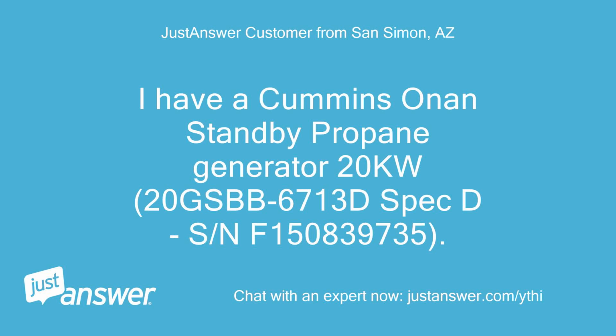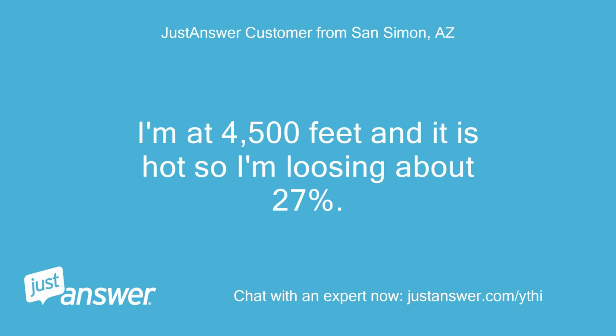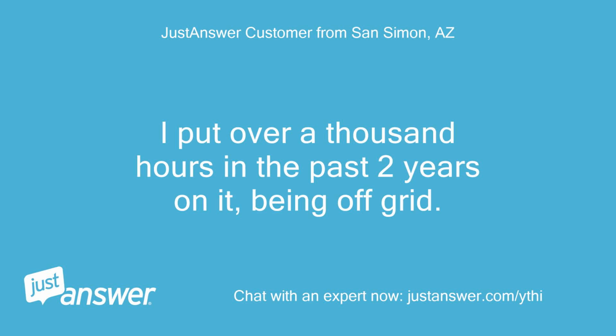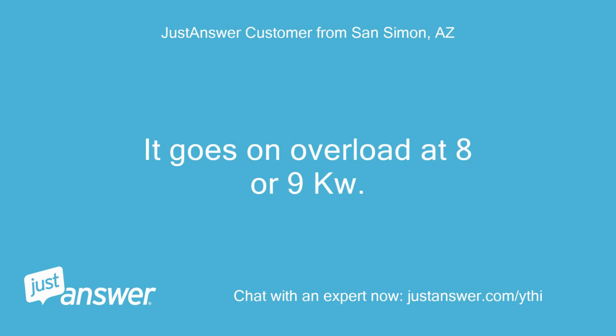I have a Cummins Onan standby propane generator, 20 kW, 20 GSBB 6713D Spec D, S/N F150839735. I'm at 4,500 feet and it is hot, so I'm losing about 27%. I put over 1,000 hours in the past 2 years on it, being off-grid. It goes on overload at 8 or 9 kW.